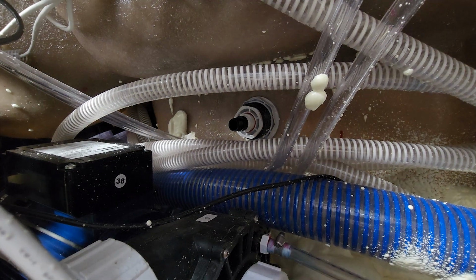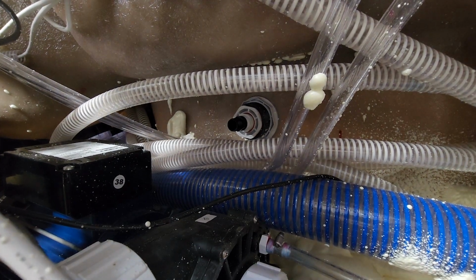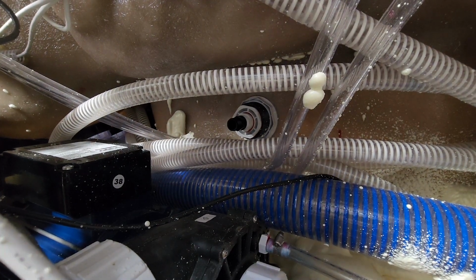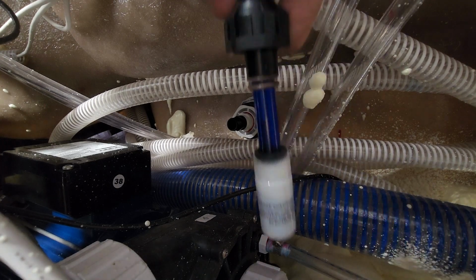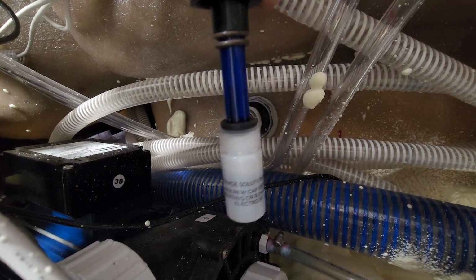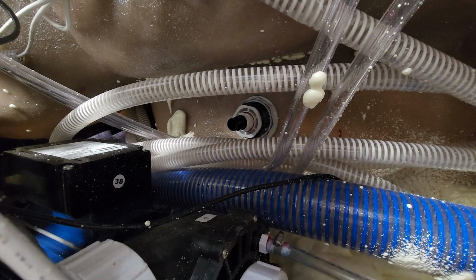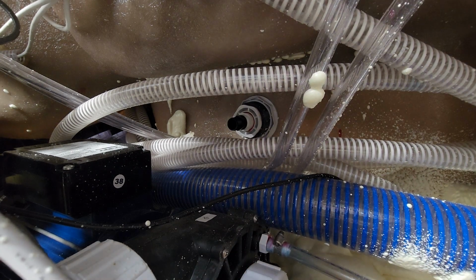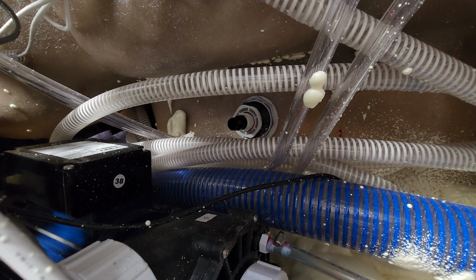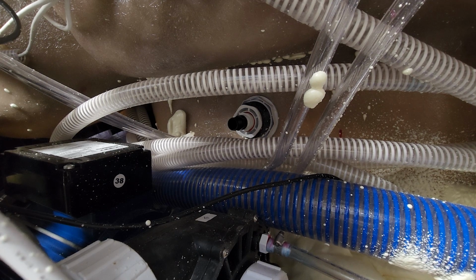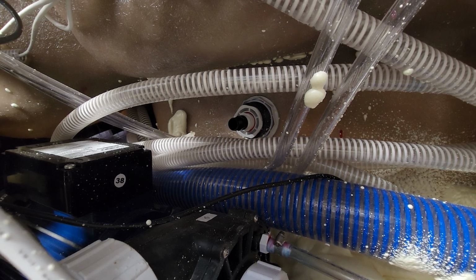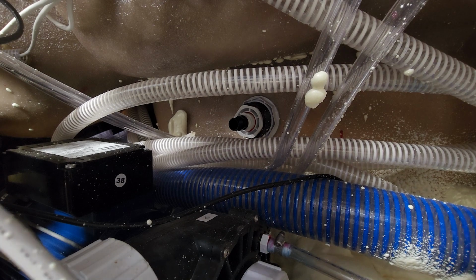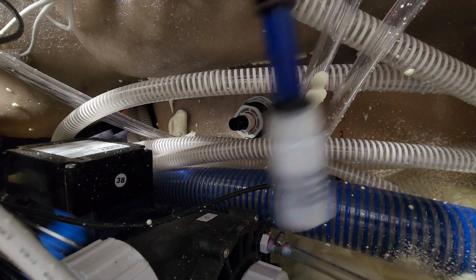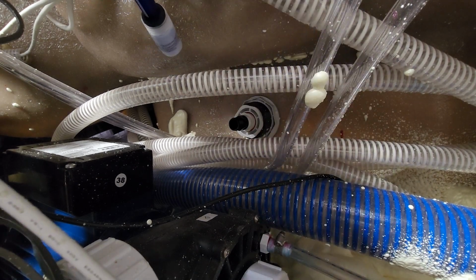Okay, so right now we're ready to put in the probe itself. We're going to take the probe off the vial, because it has to stay wet at all times. At this point, the tub should be filled above the actual probe inlet inside the tub. If that's the case, we can continue. If not, we do not put the probe in until we have sufficient water covering that inlet.